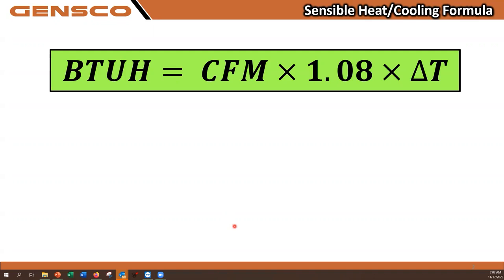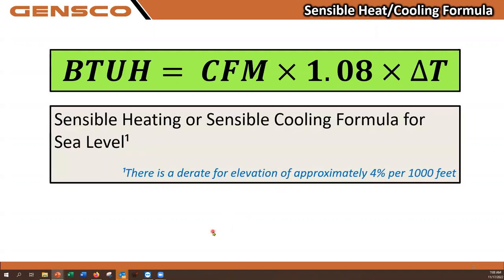The formula for sensible heating or cooling is the CFM passing through the unit times the difference in temperature times a constant of 1.08 at sea level. Now, if you are not at sea level, there is approximately a 4% derate for any output based on each 1,000 feet of elevation. So if you were doing something in Missoula at 3,000 feet, whatever you do in this formula will be reduced by 12% as an actual output. So CFM times 1.08 times the difference in temperature between the return air and the supply air.